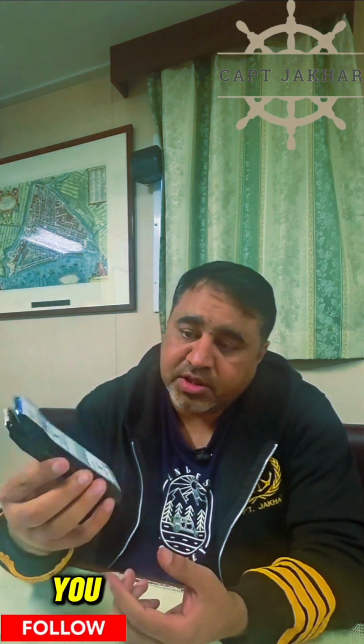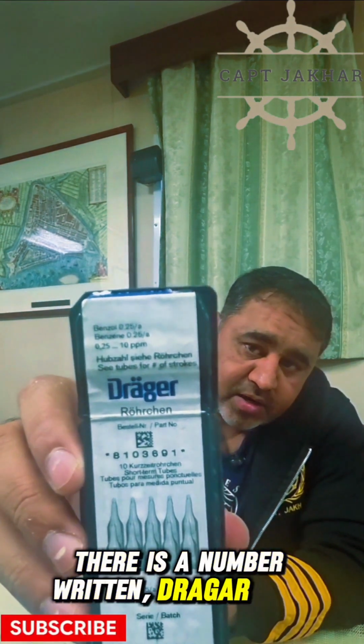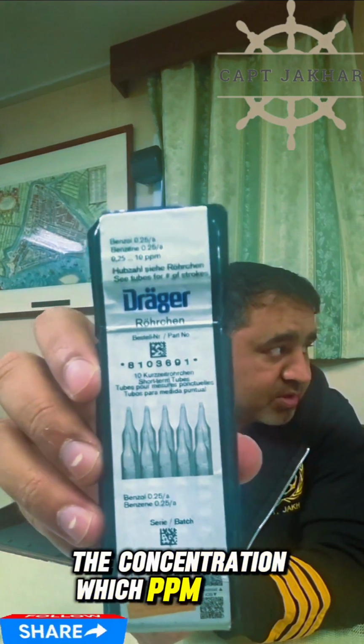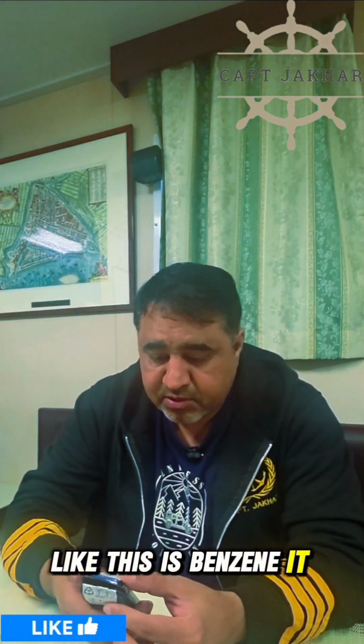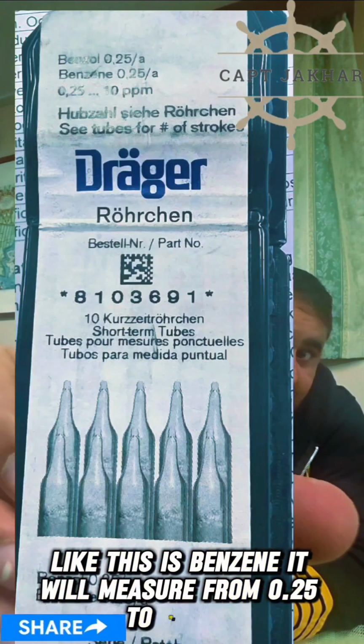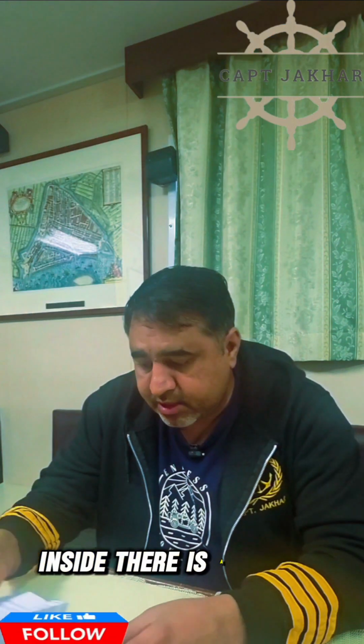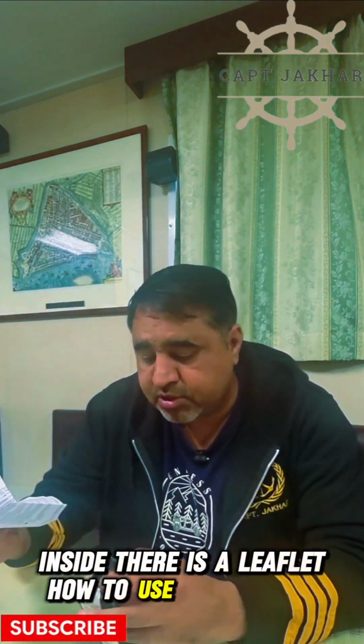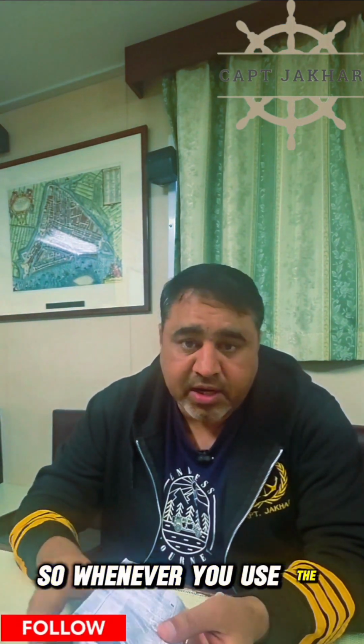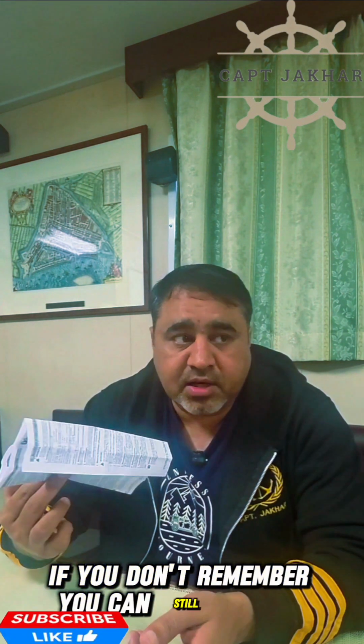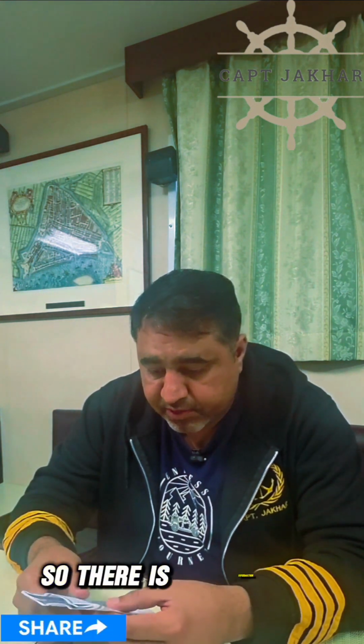This is a Dräger tube box. You can check on top. There is a number written, the Dräger tube code, and the concentration, which ppm it will measure. Like this is benzene. It will measure from 0.25 to 10 ppm. Inside there is a leaflet on how to use the Dräger tube. Whenever you use it, if you don't remember, you can still read it. There is information given there.